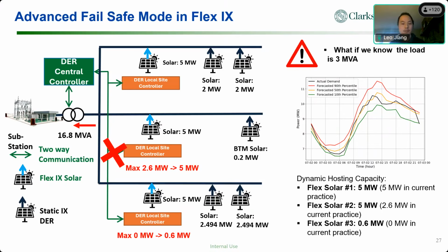Now the question is, what if we know the load is 3 MVA, or 3 megawatt? Now you know that you can use the load profile to update this static hosting capacity to come up with a dynamic hosting capacity, and use that number to update the controller.